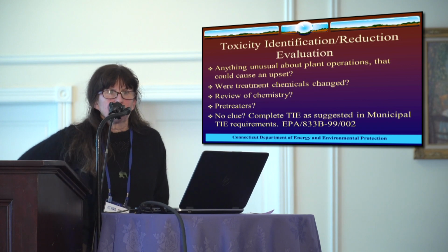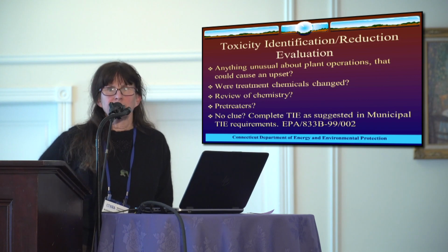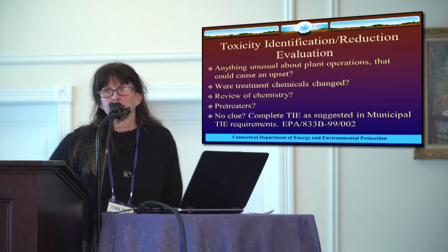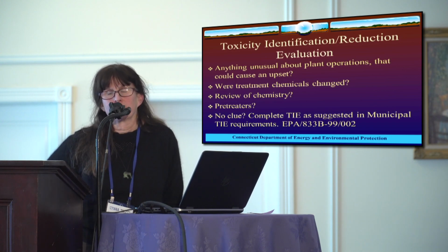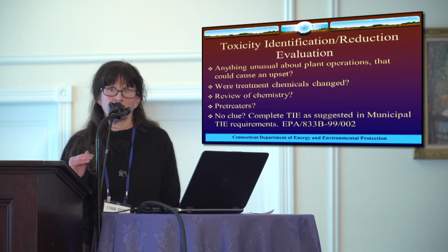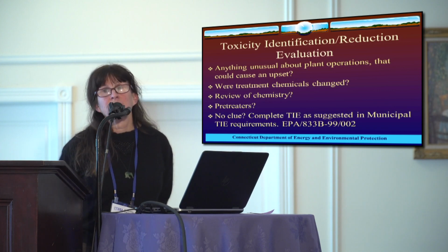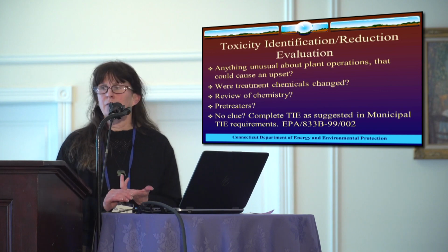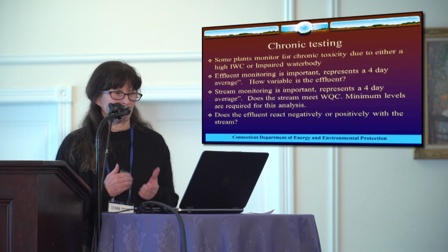Now, in Connecticut, we use toxicity identification evaluation or toxicity reduction evaluation, and we mean the exact same thing. So we don't need to know that polymer X caused all your problems. What we need to know is that polymer X at concentration Y won't. So we need to know that you've taken care of the toxicity. We don't need to know specifically what caused it. And then the most important thing is I need a final memo or report saying this is what we did, this is how we solved the problem, we've passed our 3 tests in a row, and then we can sign it off as done.